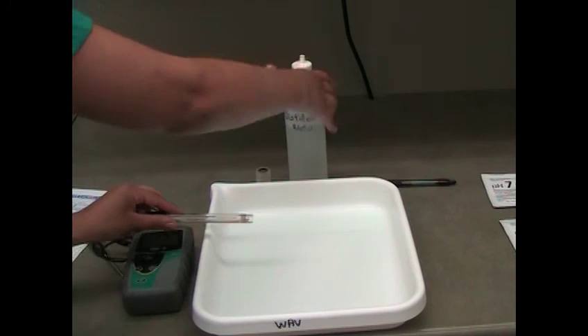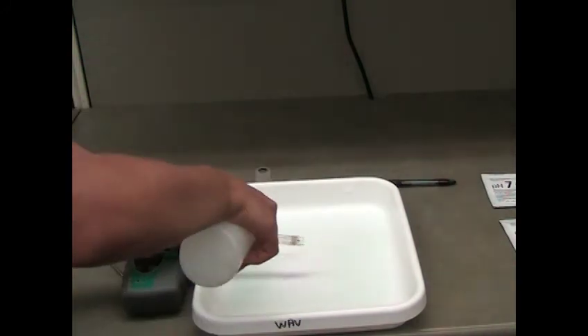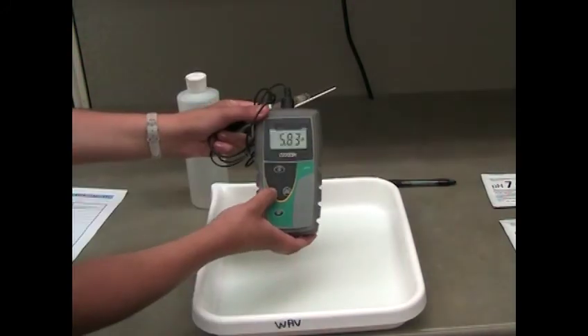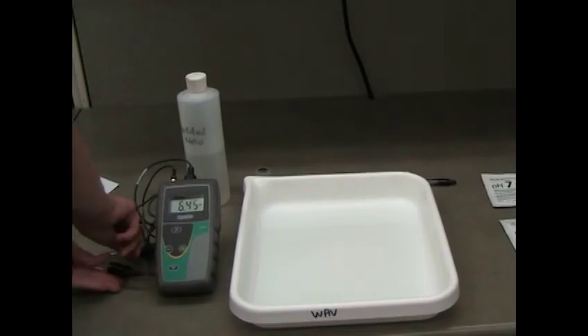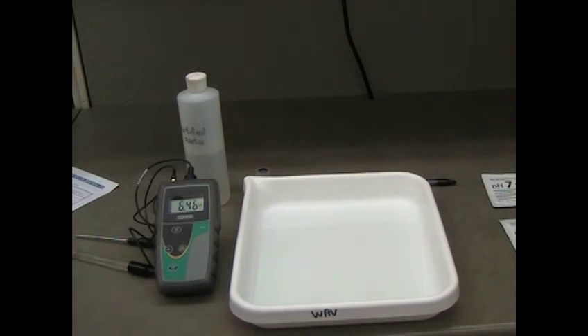Rinse the electrode with distilled water and shake off the excess. Press CAL on the pH meter to begin the calibration process. The letter CA will appear on the screen. Once you enter the calibration mode, the pH symbol and reading will flash on the screen.